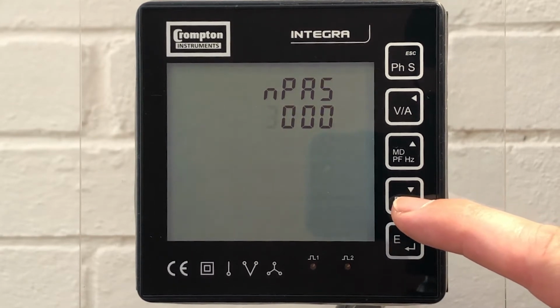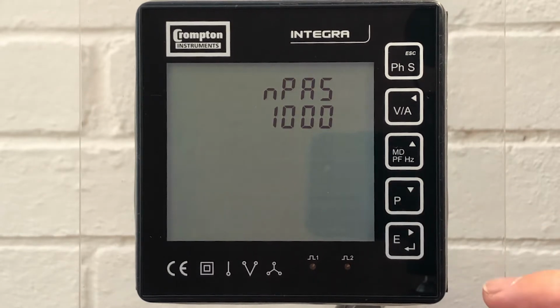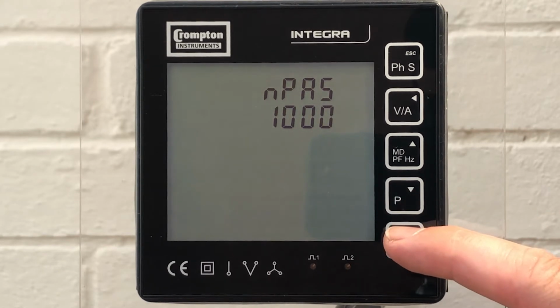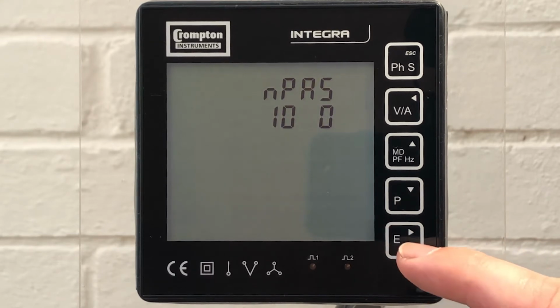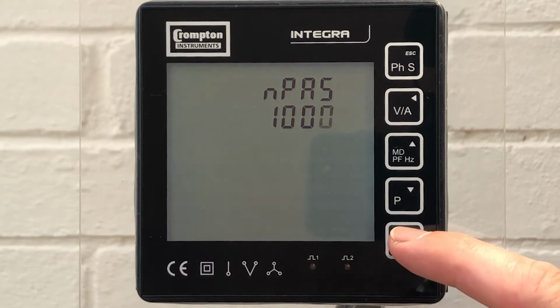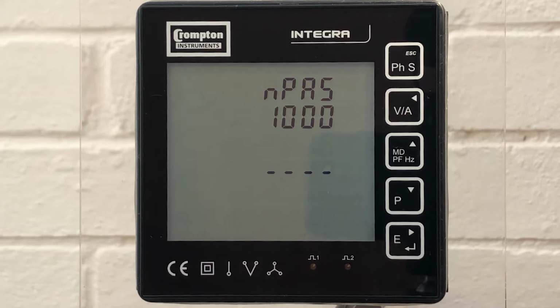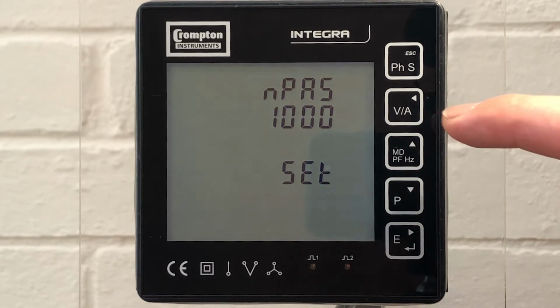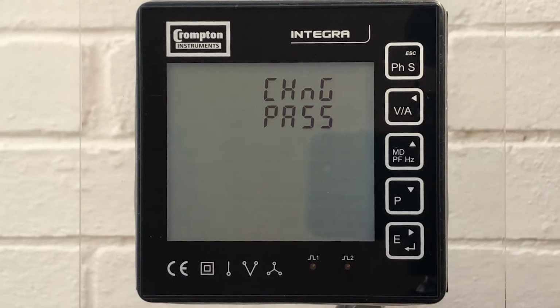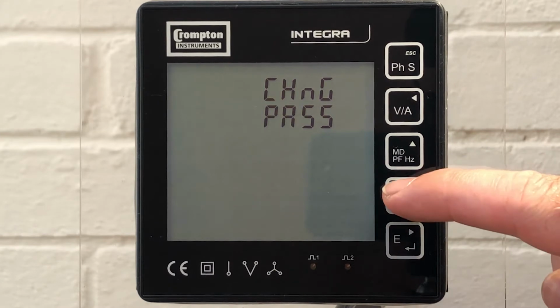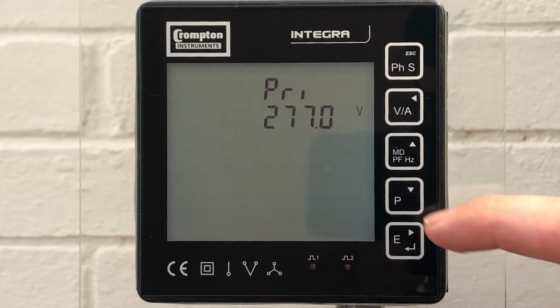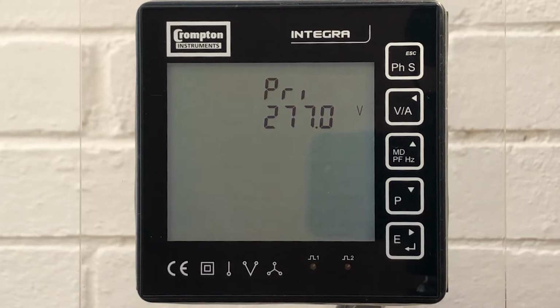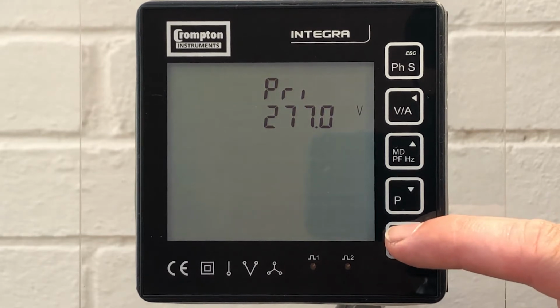Change the first character using the up and down arrows, and a press of the E button moves on to the subsequent characters, which can then be changed in turn. In this example, I'm setting the password as 1000 and holding E until Integra says set. Press the VA button to escape and arrow down, down again, and this is the primary voltage setup screen.